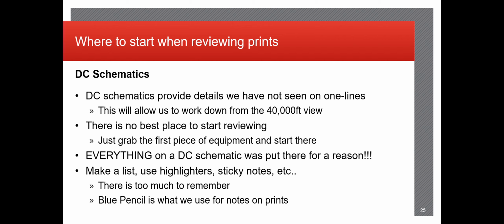Usually, there's not really a best place to start reviewing, depending on the project, in my opinion. If it's a greenfield and nothing's in service, you can really start wherever. Usually try to start with, like they said, DC schematics. Verify that all the equipment is there, properly hooked up, the wires are in the correct place before you even turn anything on, any power to the equipment. And then make sure you make a list and highlight as you go along.